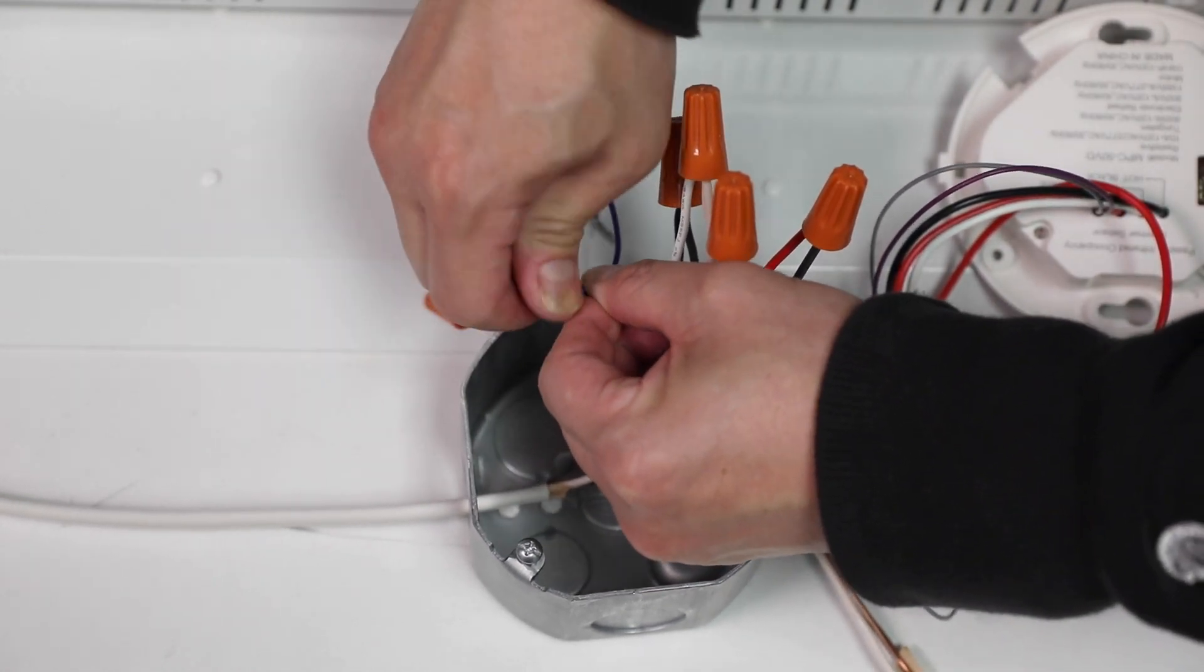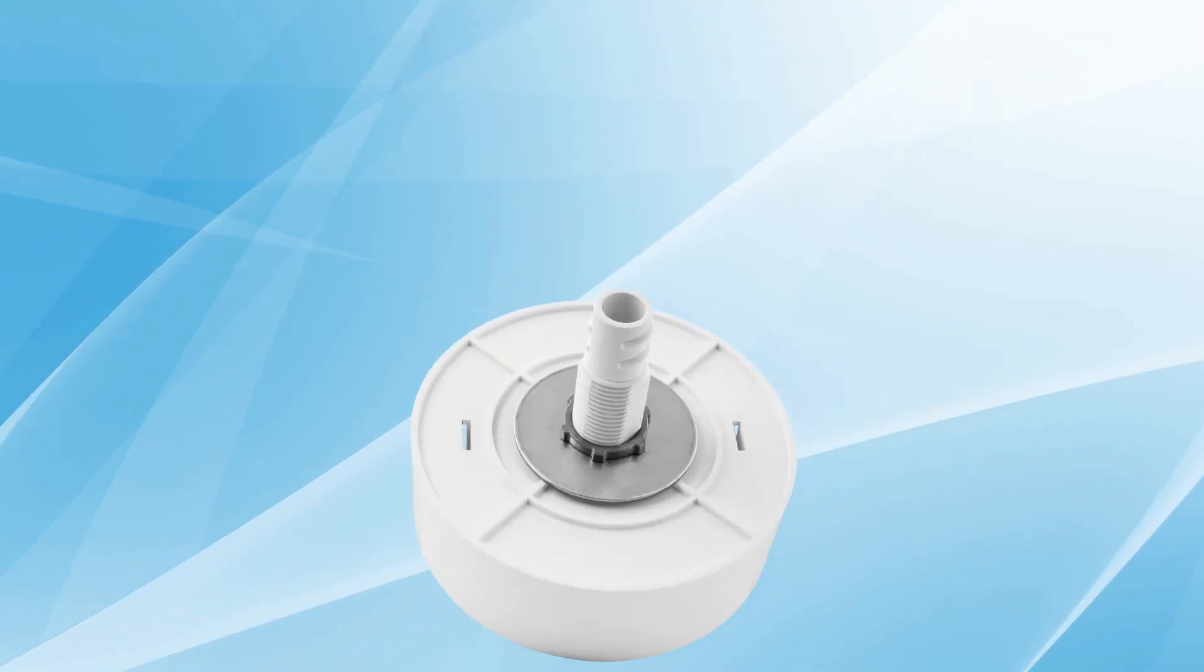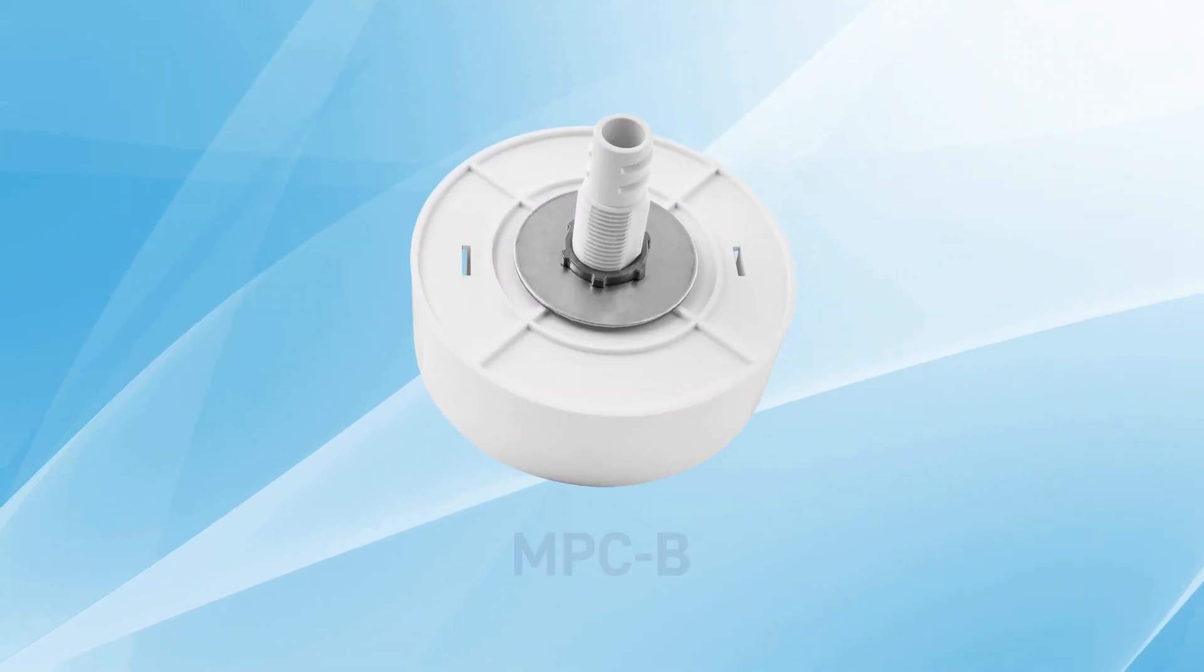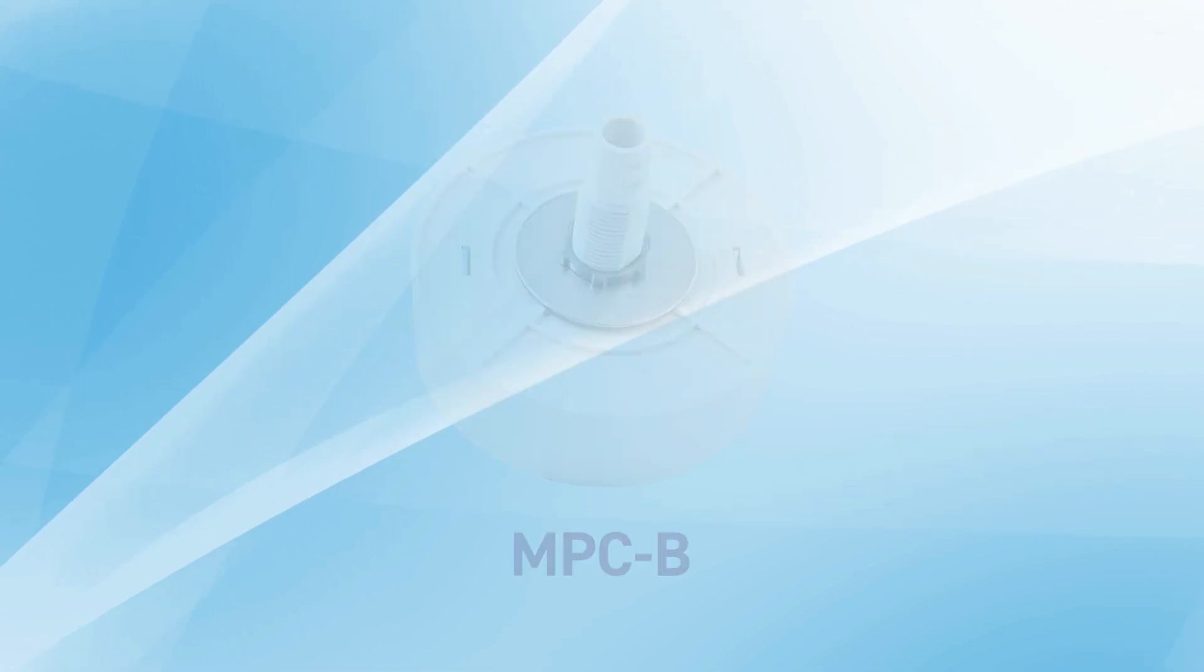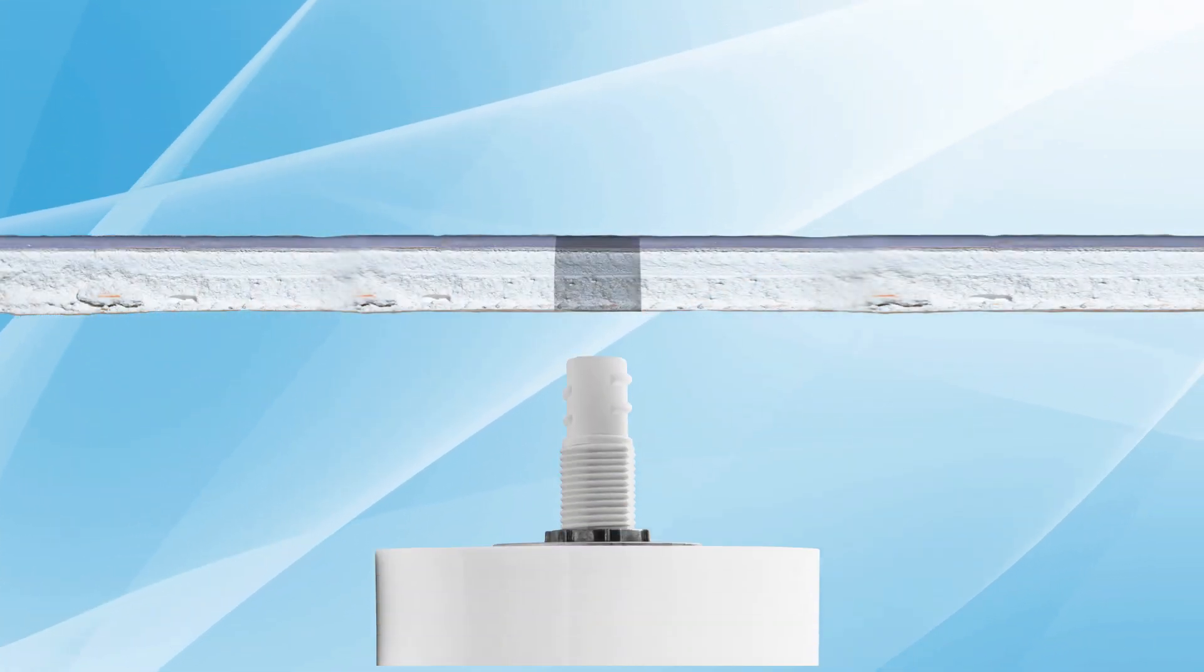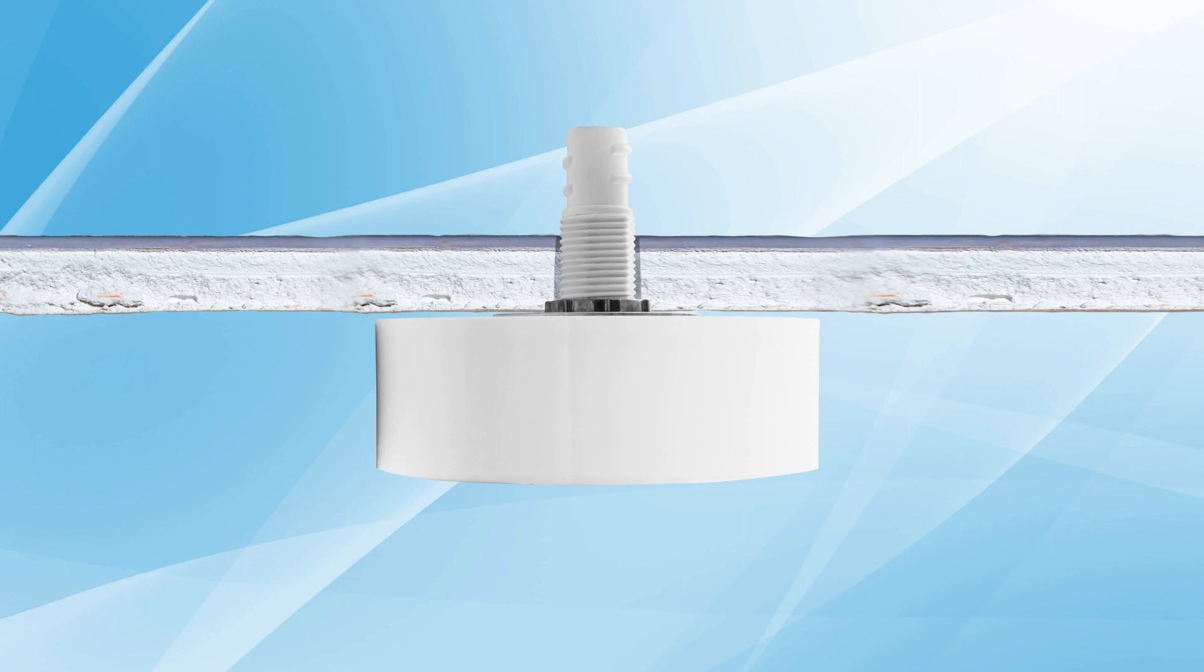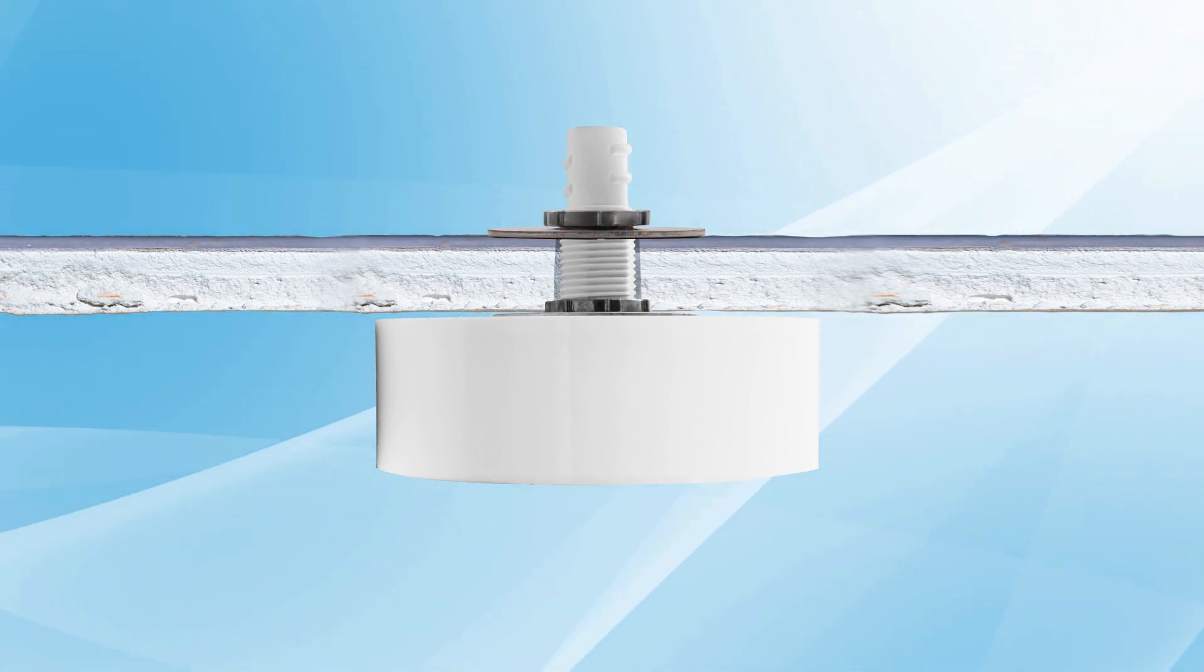If installing the sensor directly onto the surface of the ceiling or ceiling tile, use the MPC-B surface mount adapter. You will need to cut a three-quarter inch hole on the ceiling. Insert the flex connector side of the adapter through the hole, then secure it with the connector nut before connecting the sensor wires.